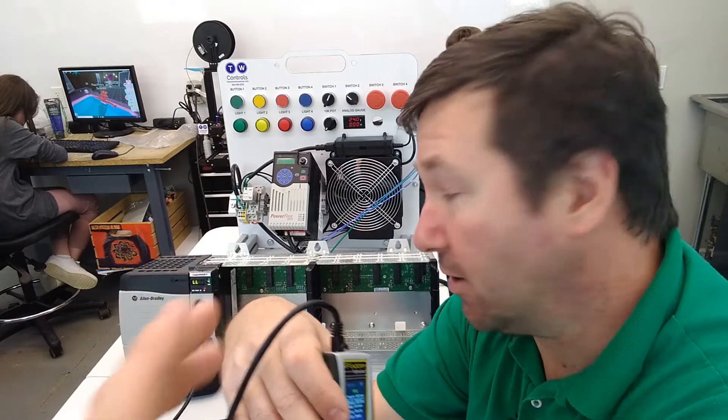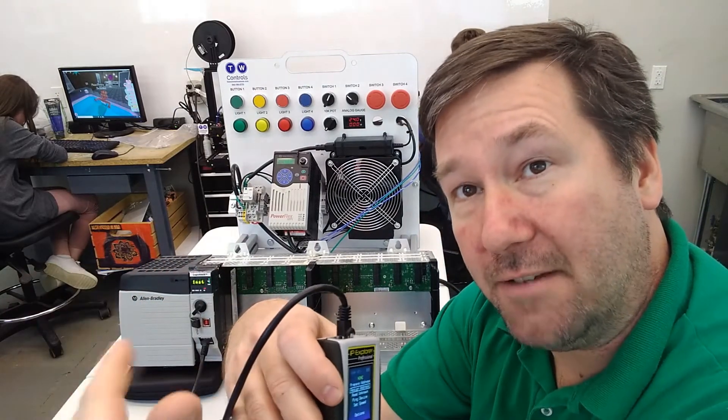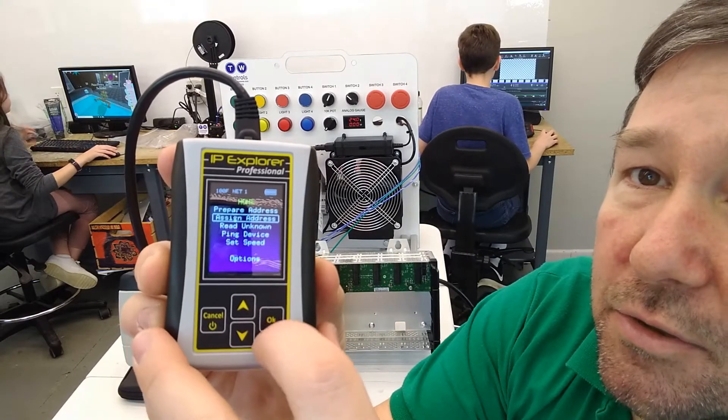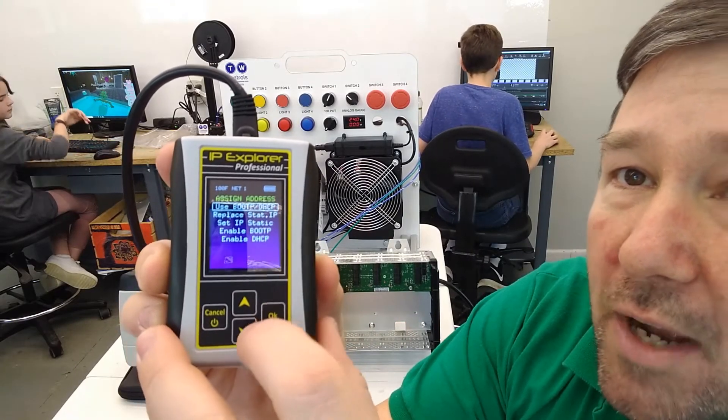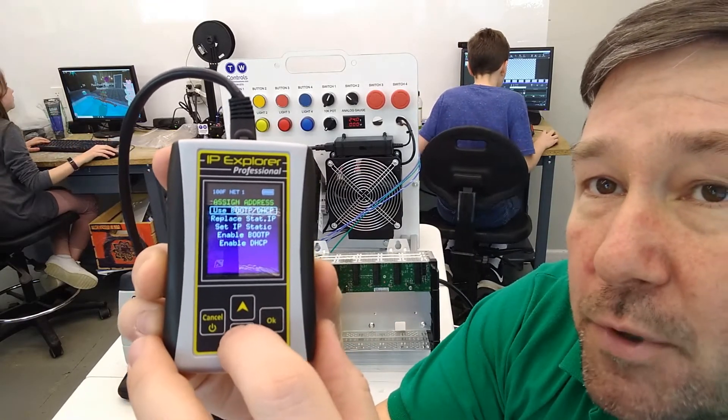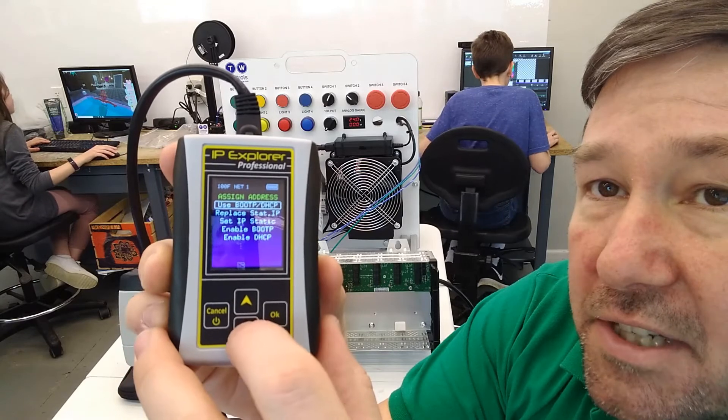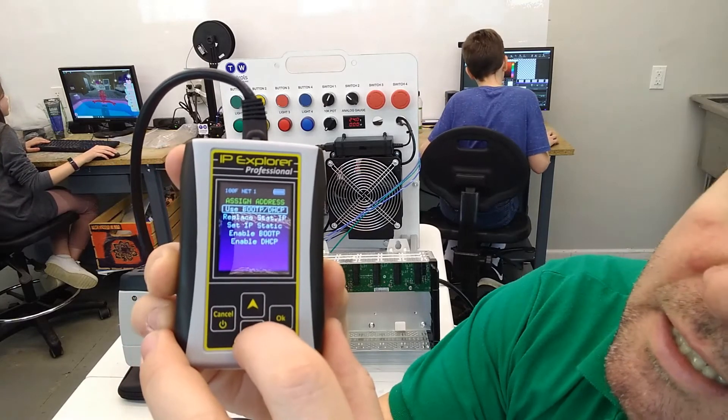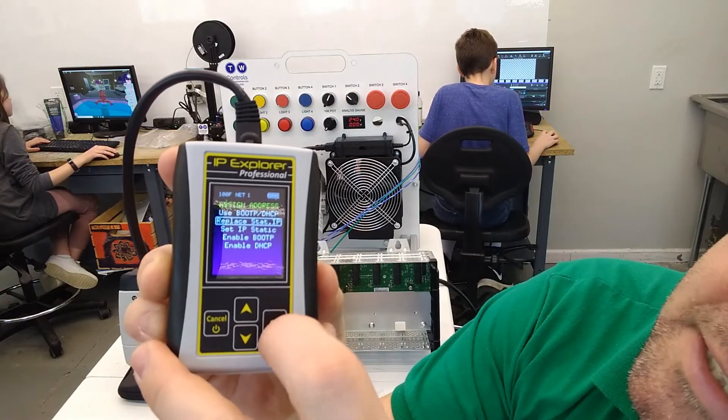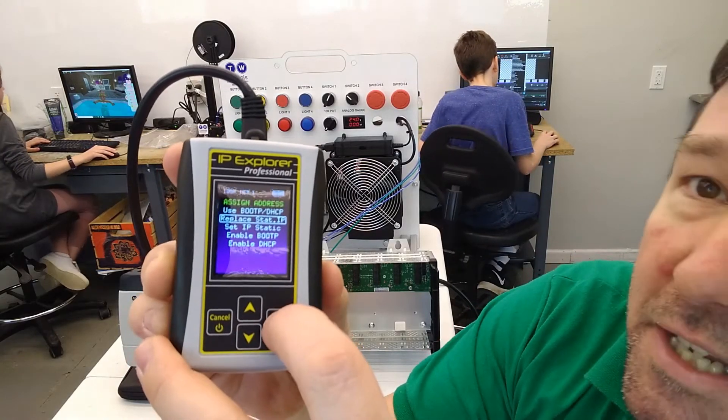Let's say I accidentally assigned the wrong address to this ControlLogix. I can change it even though I've set it to static. So if we go back into assign address, and instead of use BOOTP/DHCP, let's go down to replace static IP.